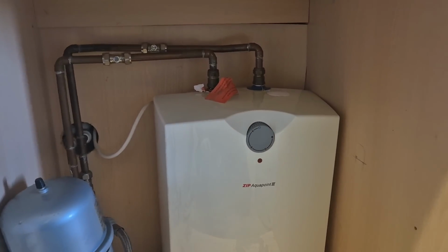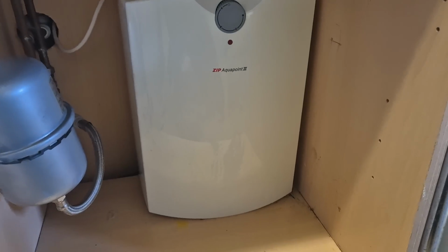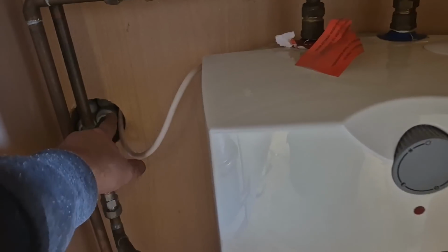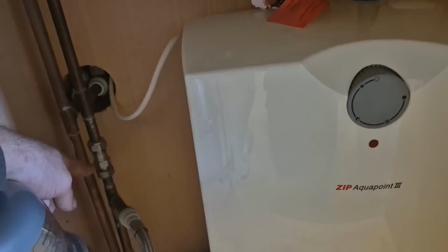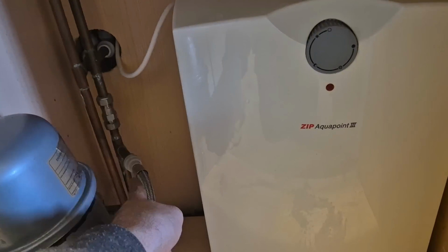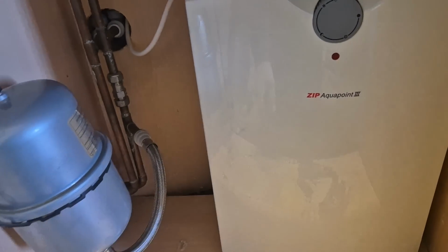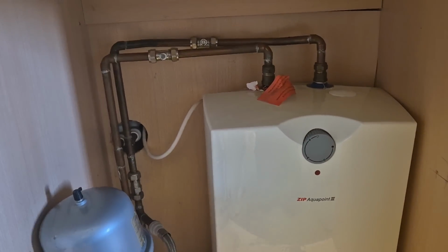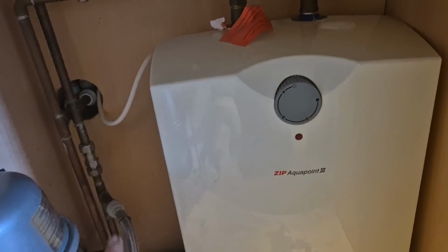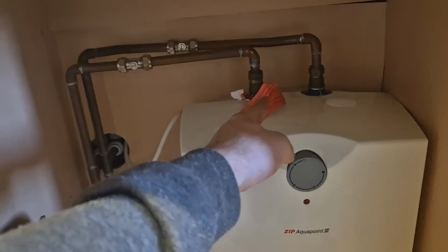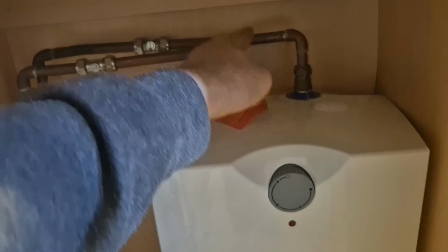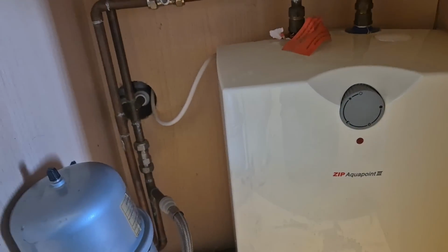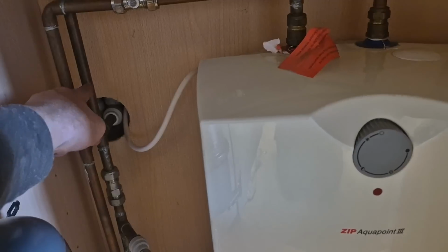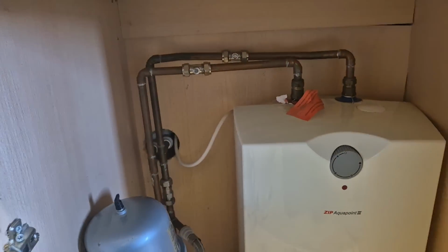Can anybody see what's wrong with this water heater? This is another one that's blown up or split. Absolutely water flying out everywhere. We've got water coming into the unit, into the heater. Check valves that side so it never expands, and then we've got no PRV on this unit either. But that expansion vessel is doing nothing because as the hot water tries to expand, it can't, because it can't go back through that check valve. So that check valve should have been there with the expansion vessel there and then the PRV. So it's plumbed in completely wrong.